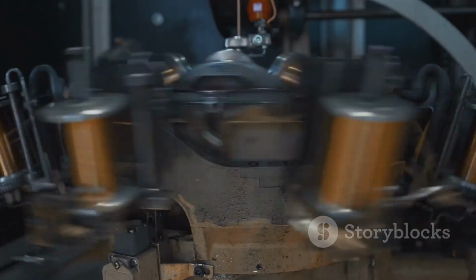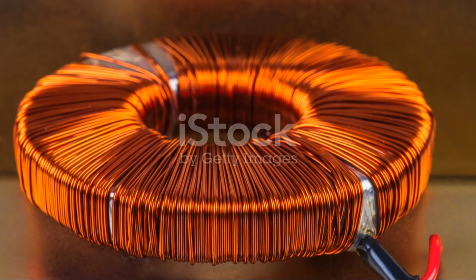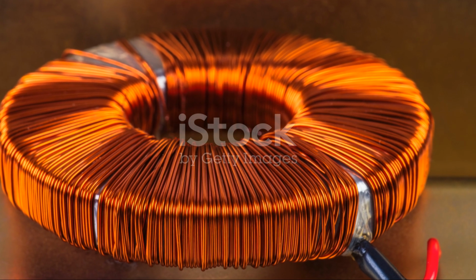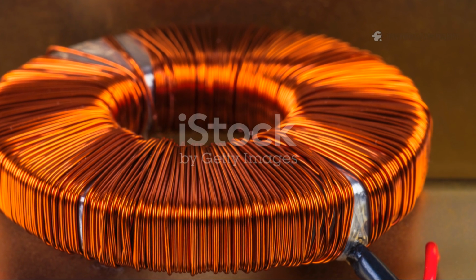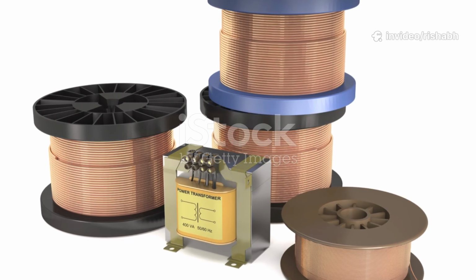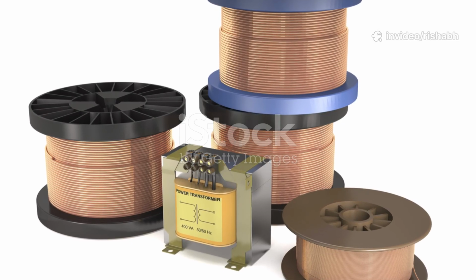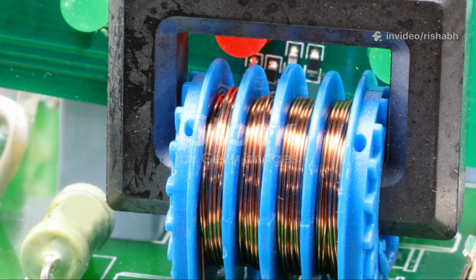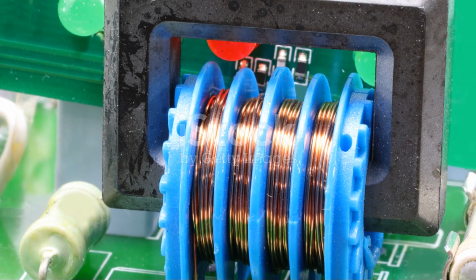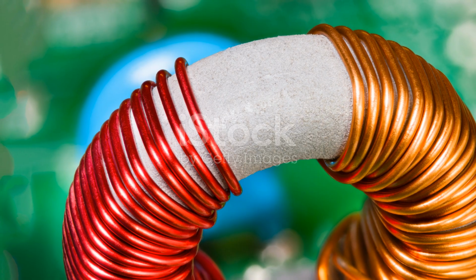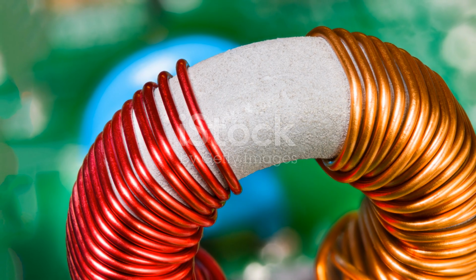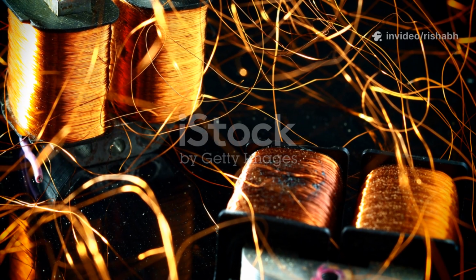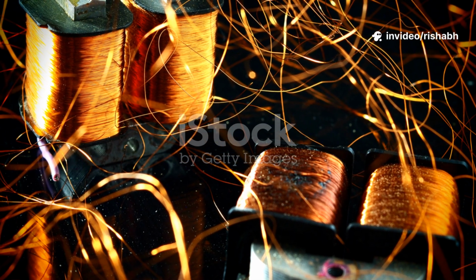Now, let's wrap our core in the conduits of power, the windings. These are the coils of copper or aluminum wire that carry the electrical current. In a power transformer, we typically find at least two sets. The low-voltage winding is made of thicker wire as it carries a higher current. The high-voltage winding, carrying a lower current at a higher potential, is made of thinner wire.